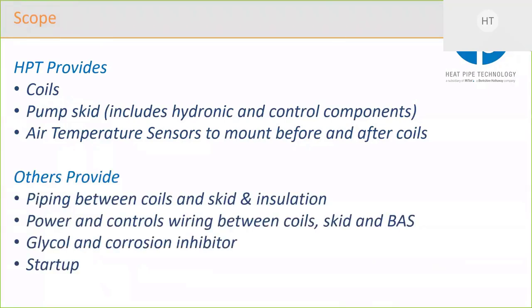Others provide the piping between the coils and the skid, and also insulation, the power and the controls wiring between the coil, skid, and BAS. So the controls wiring, for example, is for the air temperature sensors and wiring to the BAS, and glycol and corrosion inhibitor, and the startup process. So that's all pretty standard on normal hydronic systems.